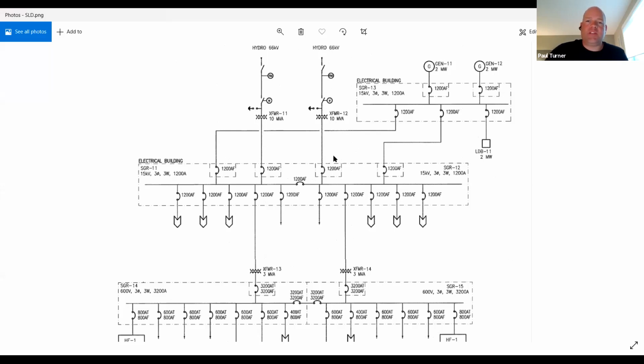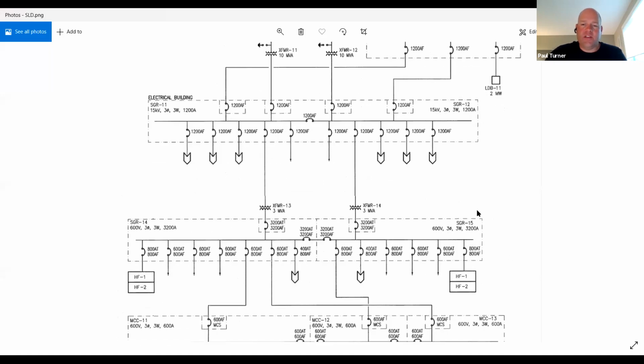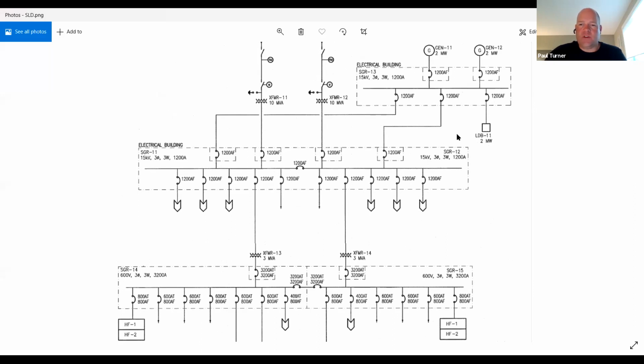But should the situation present itself that both 66 kV feeds from the utility are disrupted, that's when the diesel gensets come into play. They would be configured with an automatic switching sequence that senses the loss of the 15 kV bus in the switchgear and automatically energizes the diesel genset and closes the breakers with the interlock systems to provide power to the 15 kV bus. Typically, the automation system would then energize only the essential loads, since it's unlikely that the diesel gensets can power the entire plant. They can likely only power a particular subset of essential loads. The automation system would start to switch in those essential loads as required.